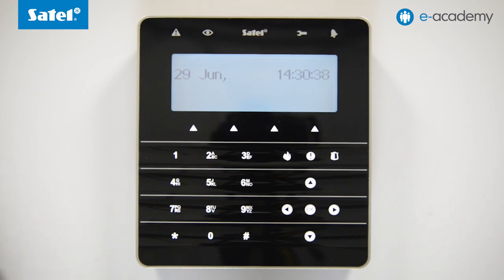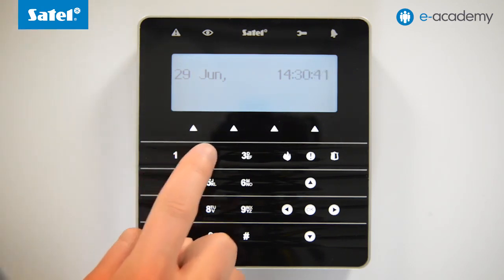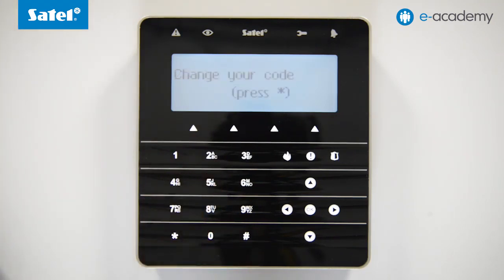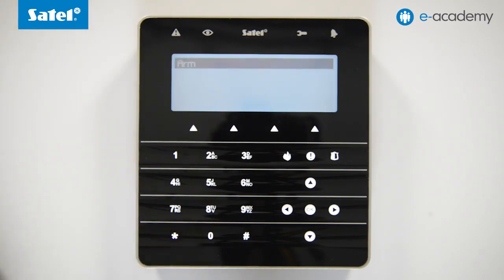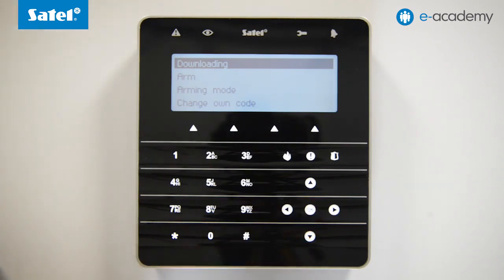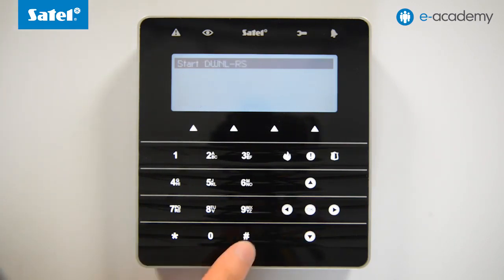Now enter the service code on the keypad and confirm it by pressing the asterisk button. The reset to factory settings has enabled the Notify of Necessity to change access code option, which is why a message about the need to change the code will appear. You can either skip it by pressing the asterisk again or set a new password. Let us skip this step in the case we are discussing today. Now select the Downloading option and confirm Start Download RS using the hash button on the keypad.